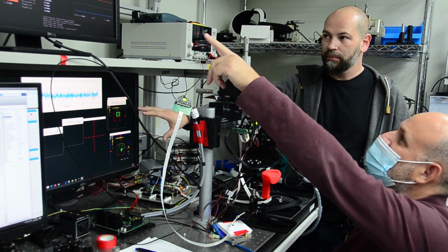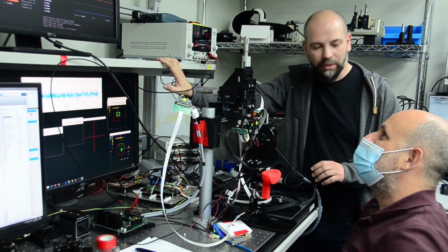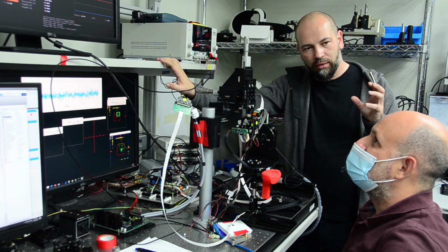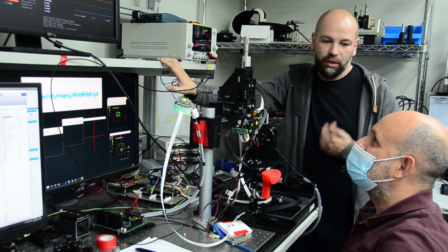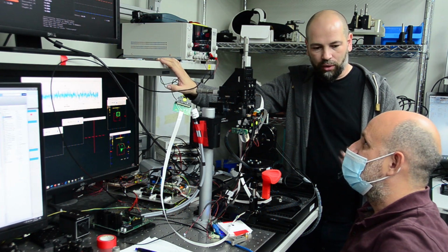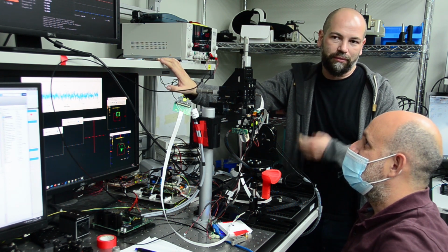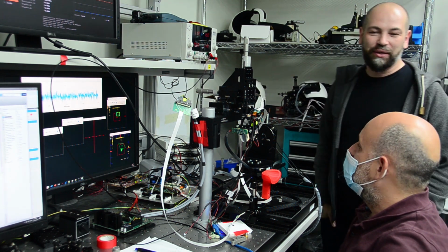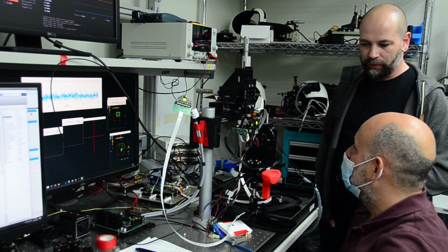What we can do is, you have two mirrors here, so the system has to compensate for at least 4 degrees of freedom. The eye can move angularly as well as laterally. So in order to compensate for at least 4 degrees of freedom, you need 4 degrees of freedom in your system. You cannot do it with less. There is a fundamental determinant issue of how you define your space of degrees of freedom.